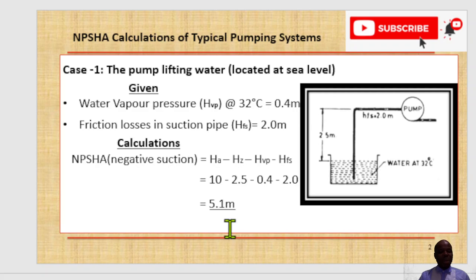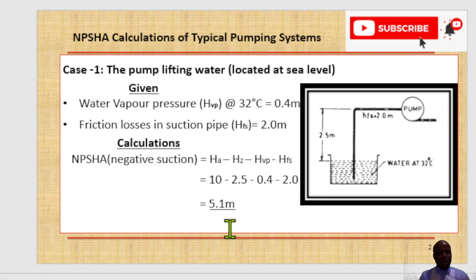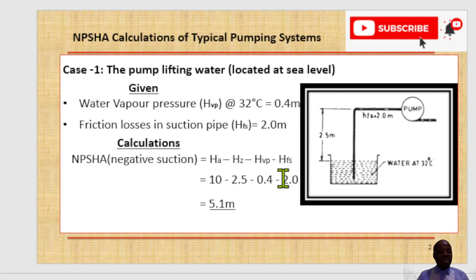You don't want to be the engineer responsible for installing a pump that is susceptible to cavitation, which is why it is very important to get your NPSHA ready. As owner's engineer or purchaser, you submit this NPSHA to your pump vendor, and when the vendor provides the NPSHR you check the difference between NPSHA and NPSHR to confirm it is in line with what is stated per API 610. In this case NPSHA is 5.1 meters.